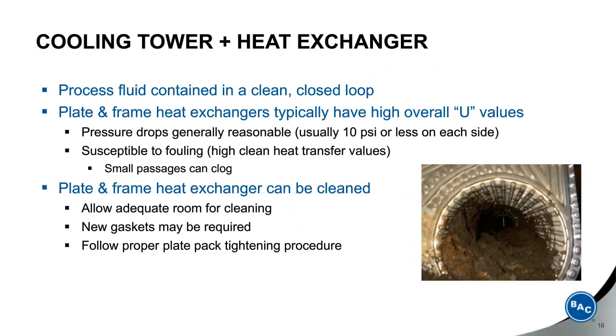Now, on a cooling tower heat exchanger system, the process fluid is contained in a clean closed loop on one side of the plates. The other side, of course, is open. The plate and frame heat exchangers typically have high overall U values, which is the overall heat transfer coefficient. The pressure drops are generally reasonable, usually 10 psi or less on each side. However, these high U values are often susceptible to fouling, so just a little bit of fouling can seriously decrease that high overall heat transfer coefficient.